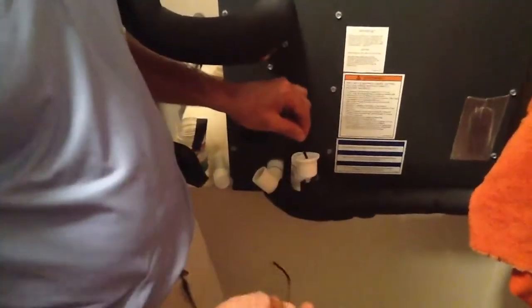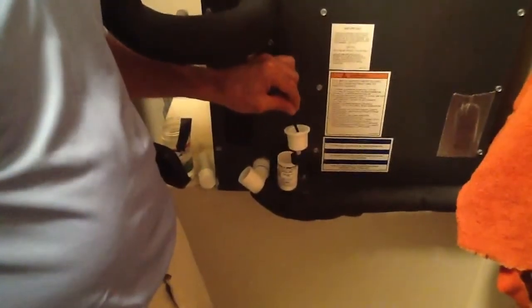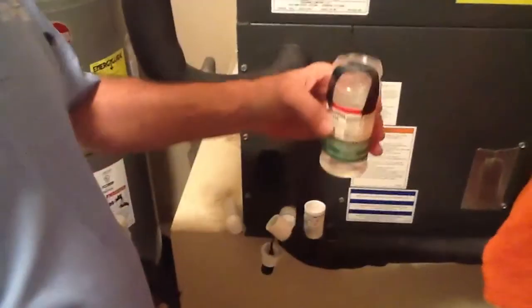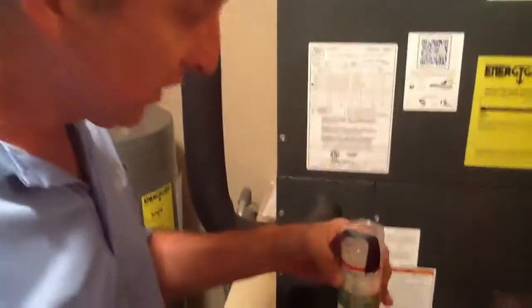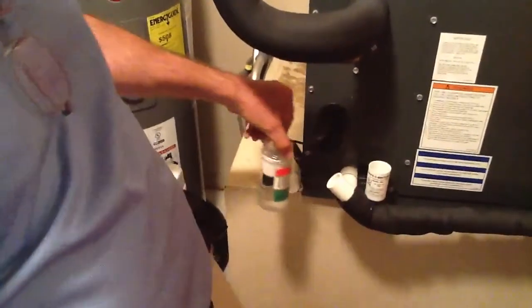I had a customer who was insistent that this particular SS2 switch doesn't work. The gentleman is pretty ingenious, so he goes and grabs a glass of water and says, 'Let's put it in that and just see how it works.' Because I couldn't get the water to stand in here since the drain is draining okay. So I'm going to take the cup and put the float switch in here.